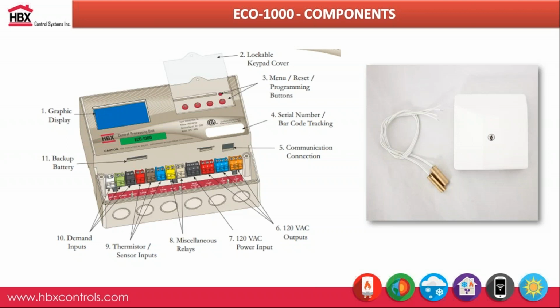In terms of the controller, there are just 4 buttons to navigate. You also see the serial number and barcode tracking. You also have a backup battery on the Eco 1000. If your power were ever to go out during a power outage, that battery is there to make sure that none of the settings get erased. We do have a built-in EEPROM on the controllers as well, so if that backup battery were ever to die, all the settings would still be saved even though there was a power outage. But it's really there to keep the time and the date on the Eco 1000, as well as make sure that all your setback options are in place during that power outage.